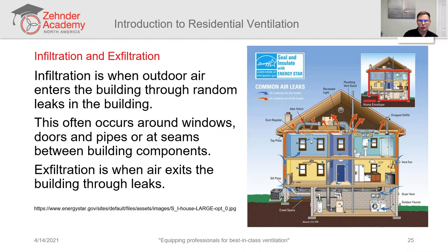We want to talk as well about infiltration and exfiltration. Here, I don't know if you can see the details of this, but basically it's just a cross-section of a typical house with typical construction features. And it's showing all the places that air leaks into a house from outside and also where air from inside the house leaks out to the outside. So you've got things like air creeping in around the sill plate, around penetrations for vents or faucets or pipes, air that can leak in through inactive exhaust vents, around construction details like top plates, things like that.